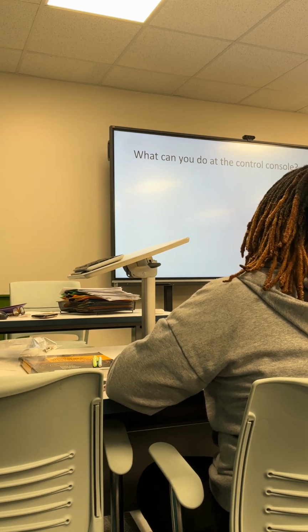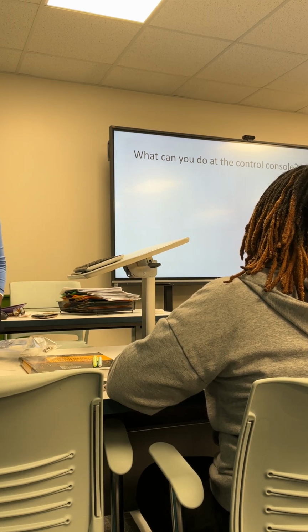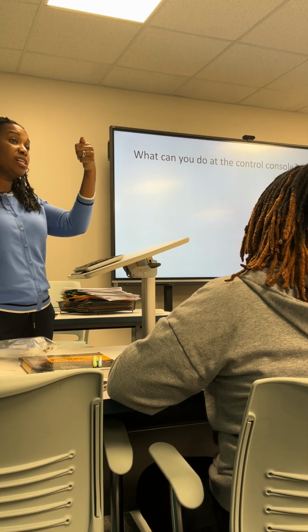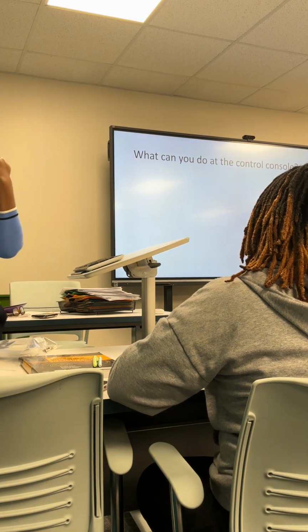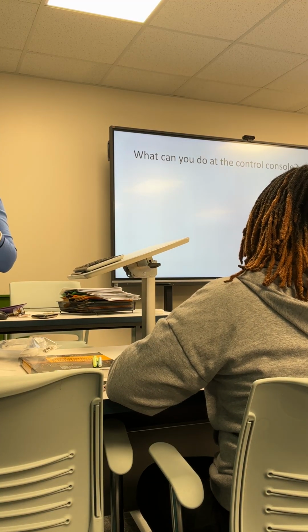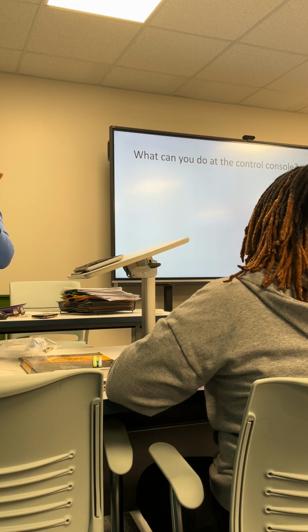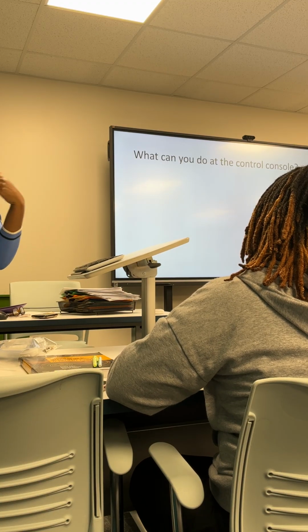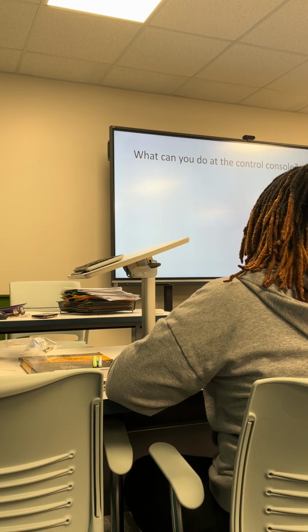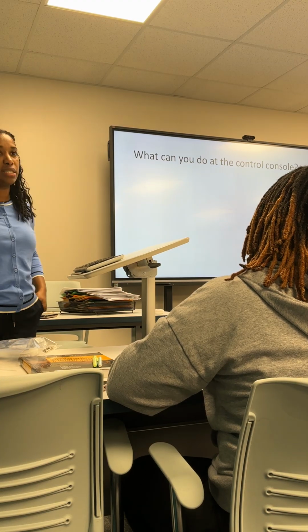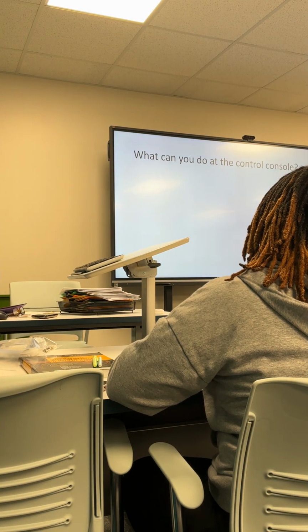Easy peasy. What can you do at the control console? You can click the button. You can control MAs and KVP and SID. Right. So MA, really, you can control time too, but AEC for time, SID is really out there. But yes, you can do all that. See the picture too. Yes.